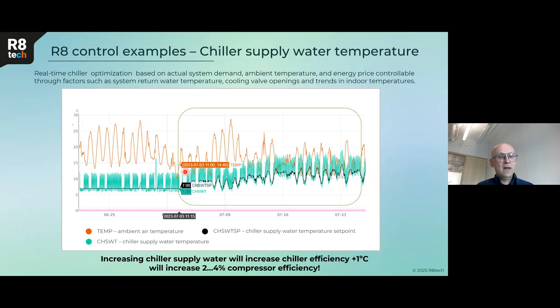And it's a very common practice that approximately +1 degree will increase compressor efficiency by 2 to 4%. So this is just an example before and after, where the supply water temperature is changing. Usually we put 7 to 12 degrees. A human will give the limits, and the AI will make the changes 24/7. Besides that, we are controlling the free cooling setting. It helps to get savings from the chiller fans, etc. And in a similar way, we are changing the heating curves as well, considering the real need. Sorry, 3 minutes.